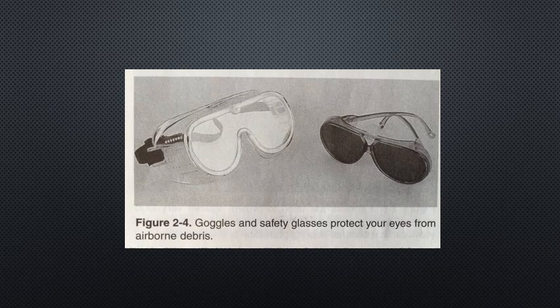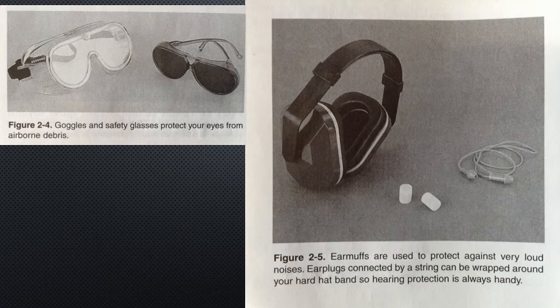Normally electricians de-energize equipment before performing work; however, there are rare times when the equipment must be live while you work on it. When this occurs, obey the following additional safety procedures: first, be sure to use insulated tools; second, wear rubber gloves and eye and face protection; third, place a rubber blanket or other suitable insulated shield over exposed live parts adjacent to the work area. Warning: Only work on energized equipment when it is absolutely necessary.